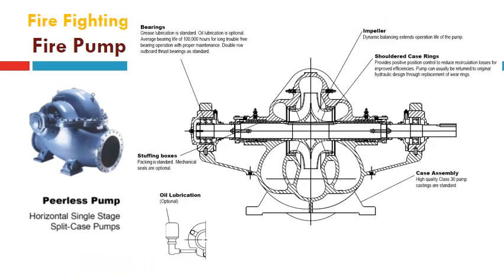This slide also presents the construction details drawing for horizontal single stage split case pumps with double suction impeller, as can be seen with all its components such as bearings, stuffing box, impeller, shrouded case rings, case assembly, and oil lubrication as optional. And on the left side we can see the pump from outside and its casing, but it is colored blue, which is not commonly used in fire, but it can be used for potable water or for irrigation or for chilled water of HVAC system. However, for fire pumps we always use the red color for the pump casing from outside, and the pump should be UL and FM approved.